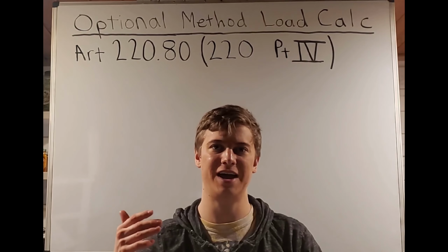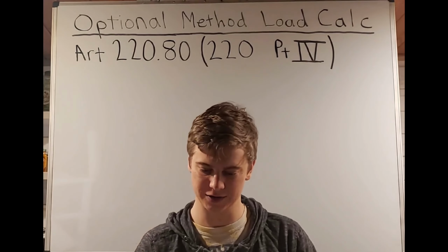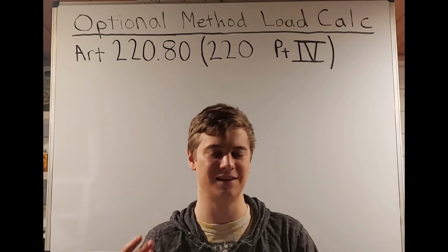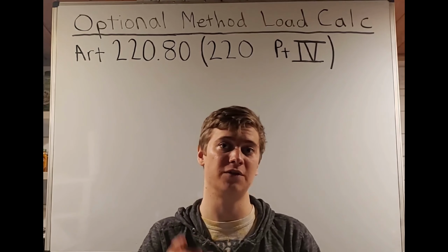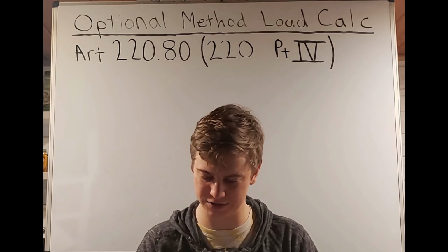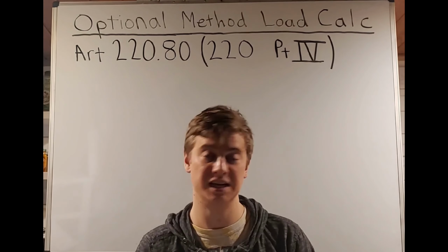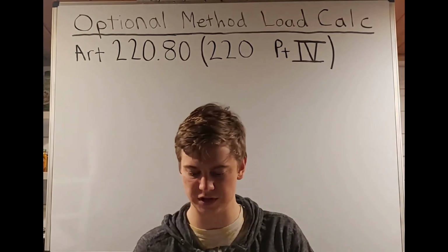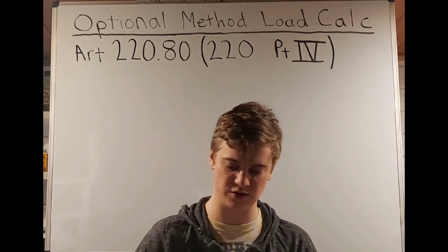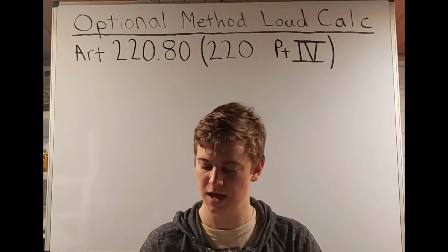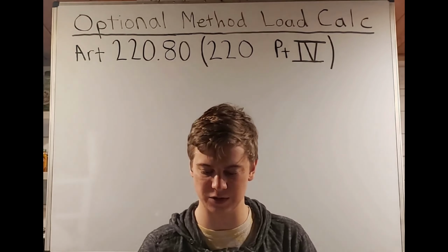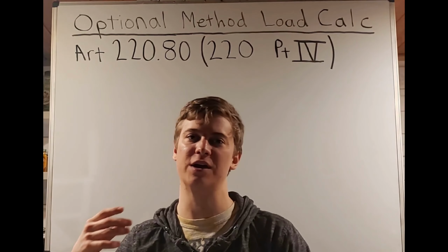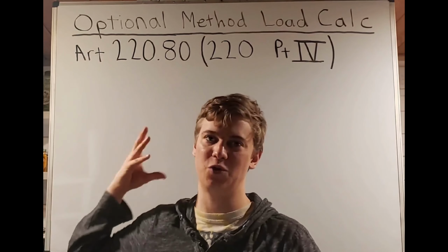Okay, we're going to look at Article 220.82 here, dwelling units. Of course, all of this is important, but I'm going to talk about the main highlights that we need to know to solve our questions and to come up with the correct answer. We see B, general loads. And I'm just going to put things in my own words here. So when calculating the general load, the first 10 kilovolt amps is going to be rated at 100%, and then the remainder is going to be rated at 40%. Okay, so as you can see, that's pretty straightforward. We're going to get into that in a second here with an actual question, an example.